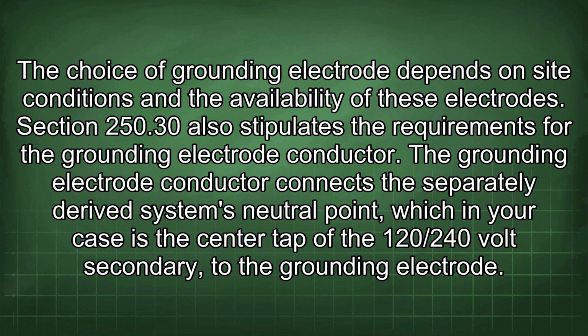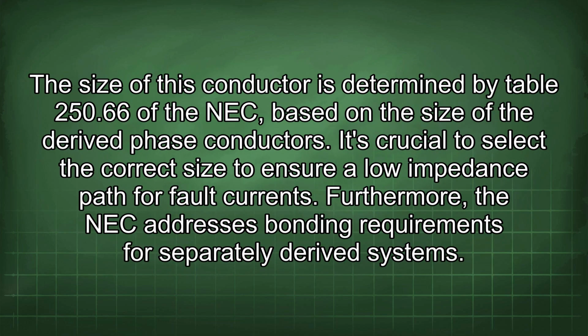Section 250.30 also stipulates the requirements for the grounding electrode conductor. The grounding electrode conductor connects the separately derived system's neutral point, which in your case is the center tap of the 120/240 volt secondary, to the grounding electrode. The size of this conductor is determined by Table 250.66 of the NEC, based on the size of the derived phase conductors. It's crucial to select the correct size to ensure a lower impedance path for fault currents.